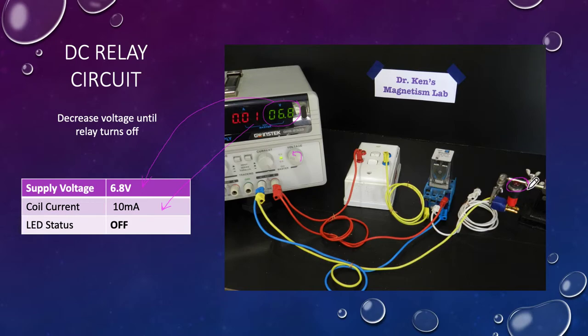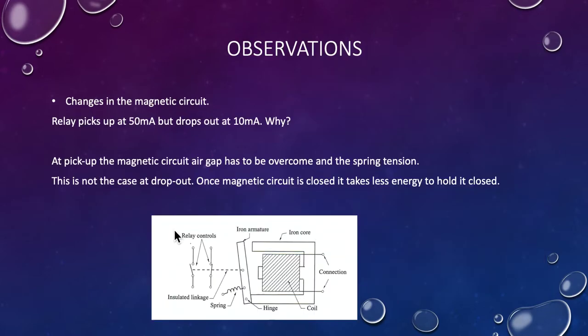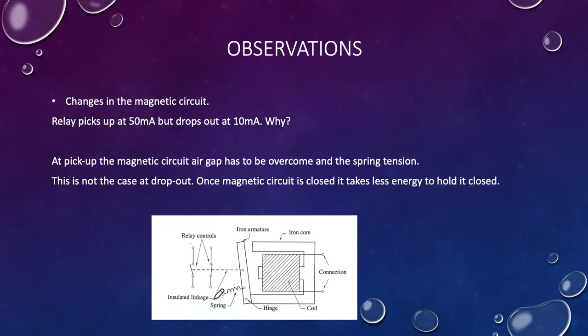What are our observations from this? First, thinking about changes in the magnetic circuit: the relay picks up at 50 milliamps but drops out at 10. Why is that the case? If we look at our drawing, here's our relay contacts physically connected to the armature. We basically have a solenoid. When we energize it, we're creating a magnetic path, and when the relay is not operated, there's this air gap, so we're going to get flux through here.